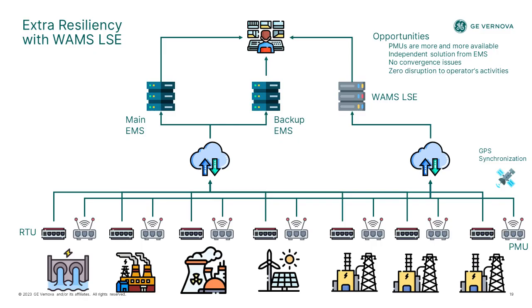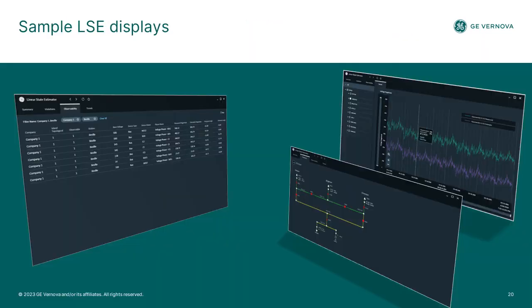One of the questions we get asked often is what level of observability do you need for running a purely WAMS-based linear state estimator? The rule of thumb is 30% coverage is usually roughly what you need to be able to run a linear state estimator. That's again because you're directly measuring the state of the grid as opposed to having to estimate the state of the grid. What I'm showing you here are some of the displays. For the linear state estimator, we have tabulars, we have trends, and we have one lines.